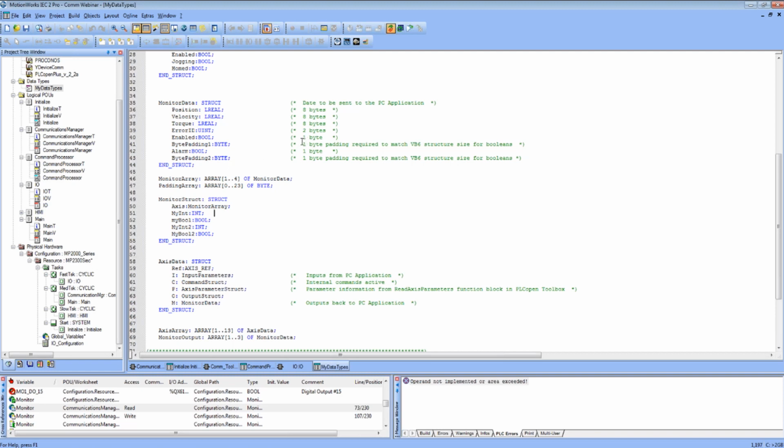The complicated part of it is you have to know how each device lays out the memory, and mainly that's the same on Visual Basic and on the IEC controller. There are some small differences which are very important, such as we realized the IEC controller is allocating an entire byte for each Boolean data variable, but on the Visual Basic side it actually defines an integer for every bool that you make.